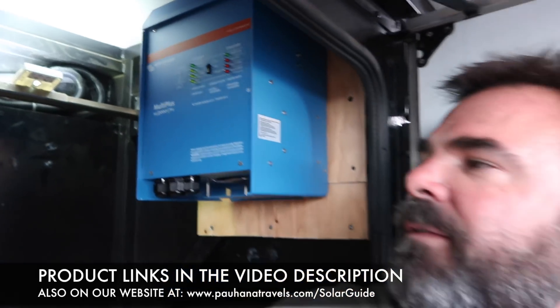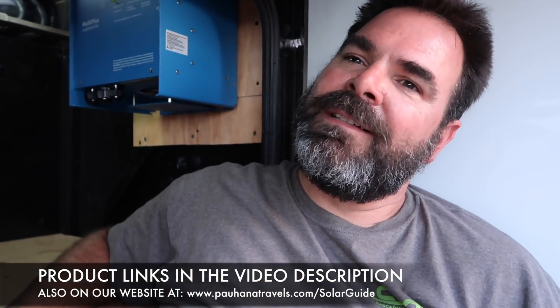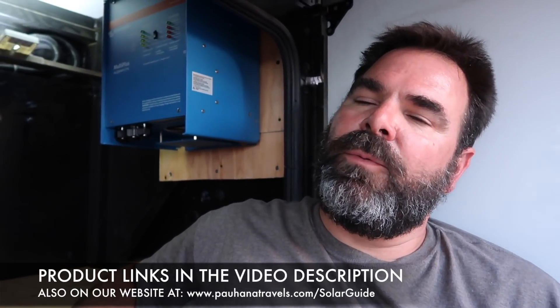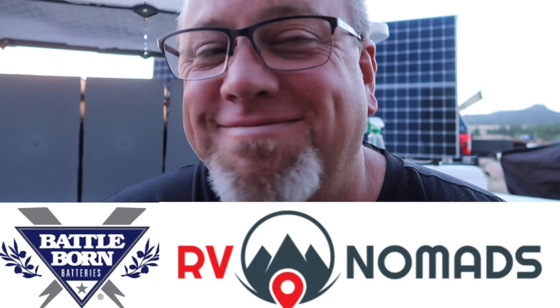But it's going to be so awesome. The Victron 3000 watt 24 volt with a 70 amp charger puts out 120 volts to the circuit breaker panel. I've got two of those. We're going to light up our circuit breaker panel like 150 amp service. We're excited. This is awesome. Epic. Elevating the story for Battle Born, our sponsors. Elevating the story for ENTV, our platform.